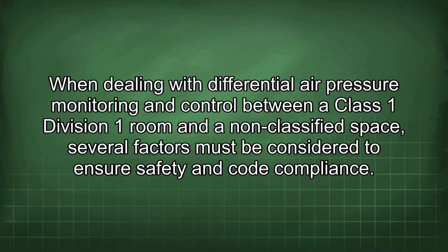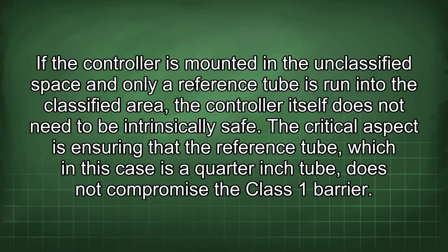When dealing with differential air pressure monitoring and control between a Class 1 Division 1 room and an unclassified space, several factors must be considered to ensure safety and code compliance. If the controller is mounted in the unclassified space and only a reference tube is run into the classified area, the controller itself does not need to be intrinsically safe.